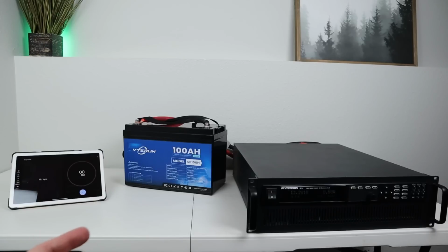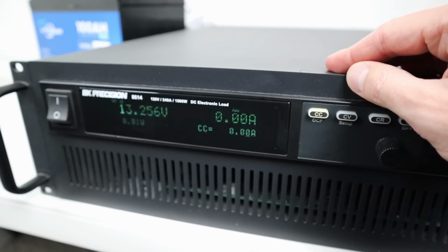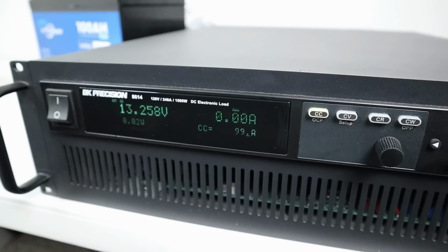In my next test, I want to see if this battery can handle 100 amps continuous output. The BMS is rated at 100 amps or 1280 watts. So with my DC electric load here, I'm going to set the amperage to 100 amps. We're going to set a timer for 15 minutes, and we'll see if the battery shuts off. So we'll set this to constant current mode. We're going to put in 99.9 amps and set that limit, and then we'll start the test.